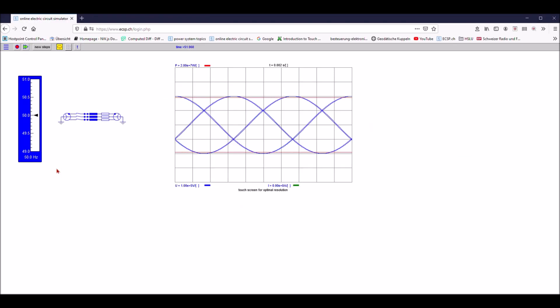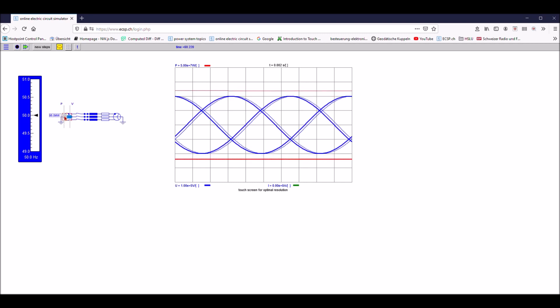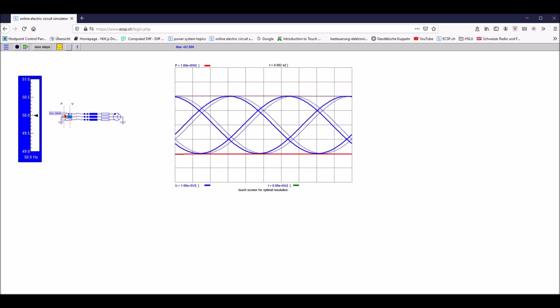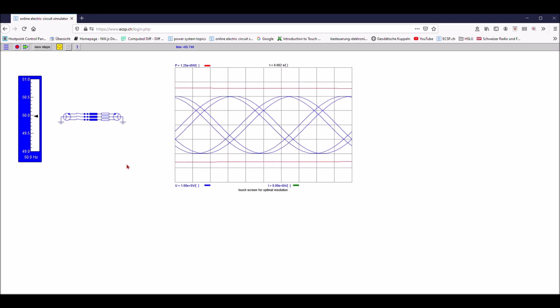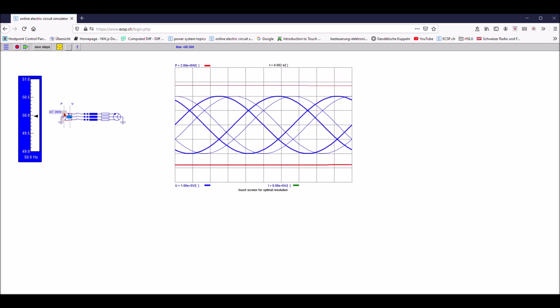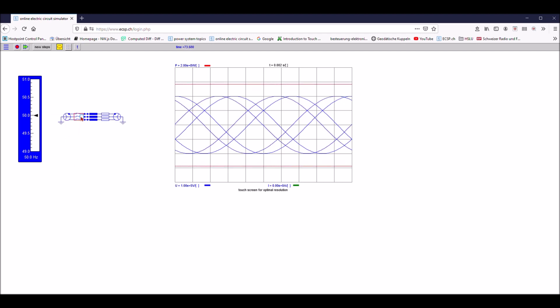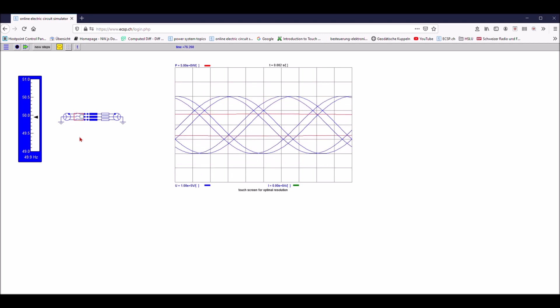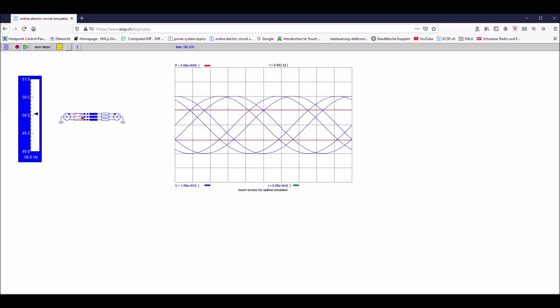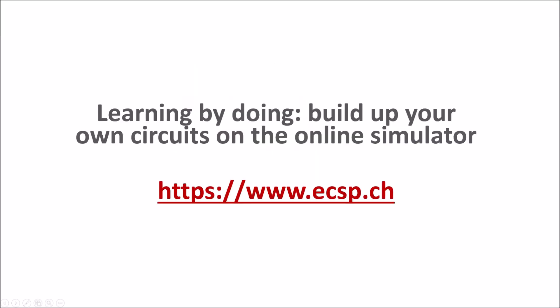You can go to the simulator and build such a network yourself. You have two generators and a line in between with some damping. By increasing the rotor angle you increase the power supply to the grid — you can see this oscillation as before. You can open and re-close the breaker very quickly and the generator stays synchronous. But if you open it for a little bit longer, you will lose synchronism. For hands-on learning, go to www.ecsp.ch — this is an online simulator where you can build your own circuits and simulate.